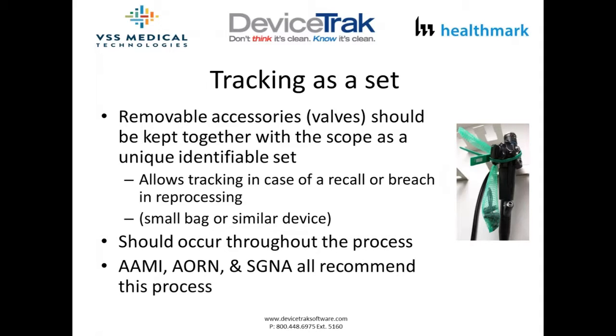Tracking endoscopes as a set means keeping all reusable removable items — valves, buttons, air-water channel cleaning adapters — together with the endoscope throughout reprocessing and storage as a unique identifiable set, using a bag or similar device. Because valves don't have serial numbers, there is no other way to track them back to the scope and therefore to the patient. This is required by AAMI, AORN, and SGNA guidelines and enables pulling everything out of circulation in the event of a reprocessing breach.